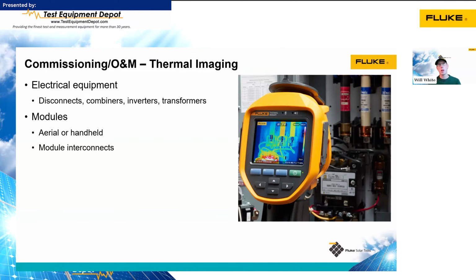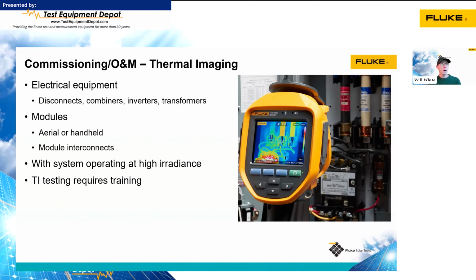It's very common when looking at modules to use aerial thermography, a drone with a thermal camera attached to it, although we can use handheld thermography to assess modules as well. The things you need to know when doing thermal imaging on solar: first off, the system has to be operating at a fairly high capacity. Usually you want 600 or 700 watts per meter square or higher, because you need that power flowing through the system to heat things up, so you can see the differential between things that are working and things that are not. Thermal imaging also requires training.